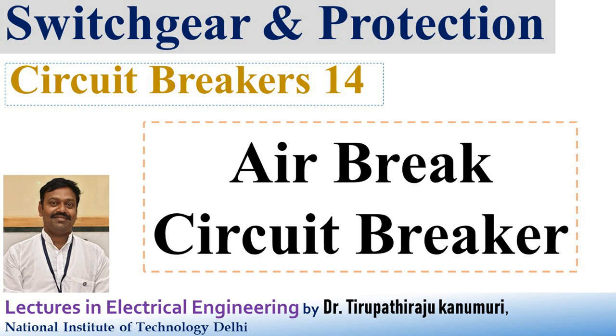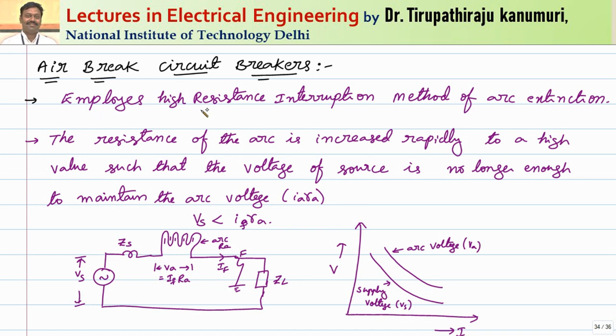Today we are going to discuss about air break circuit breakers. These employ the high resistance interruption method of arc extinction. This is based on the simple principle that the resistance of the arc is increased rapidly to a high value such that the voltage of the source is no longer enough to maintain the arc.